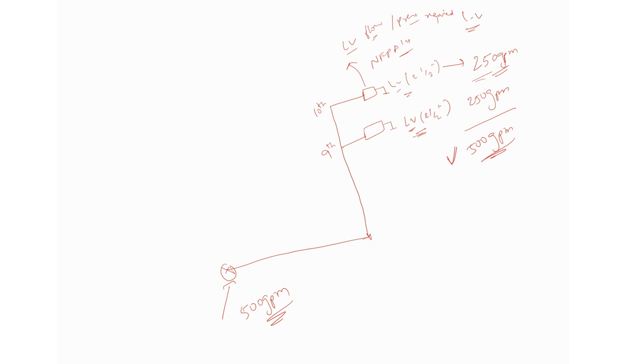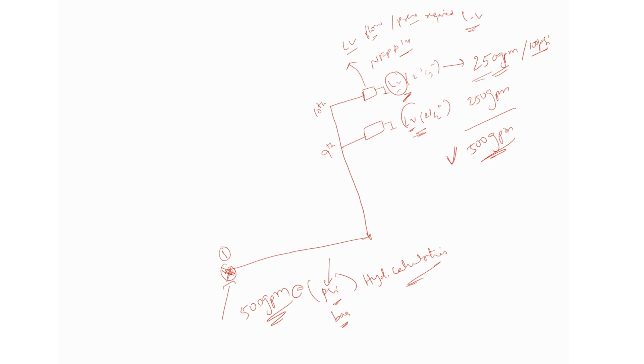We need to have the pressure requirement at the particular landing valve: 100 psi at the remotest valve. That means we need to calculate the head required — in PSI or bar — at the starting node so that the water will reach those particular landing valves with the required pressure of 100 psi.